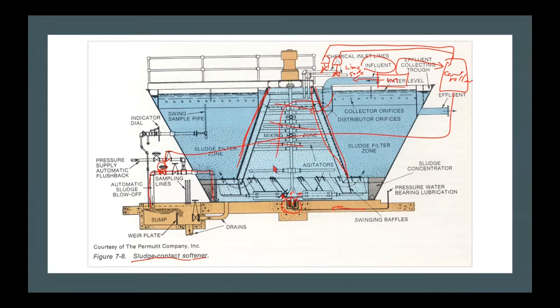So as the water mixes, it descends through, pin flocks are forming, and heavier flock is forming as well. And then we get to this bed level where the velocity has slowed down so much that these pin flocks and larger flocks simply cannot get carried through, because the force of gravity at that point would be equal to the force due to velocity of the liquid.